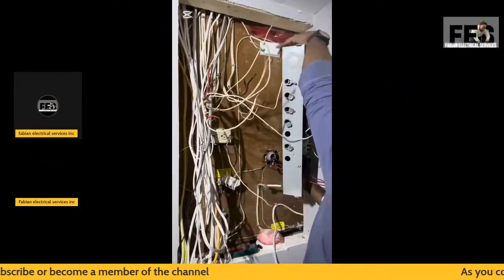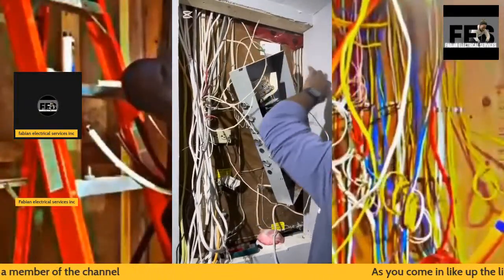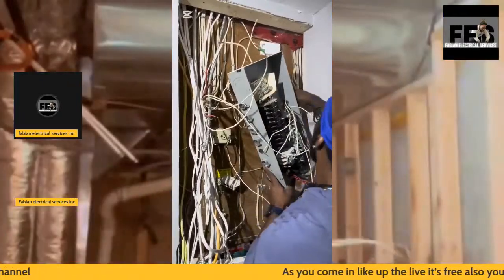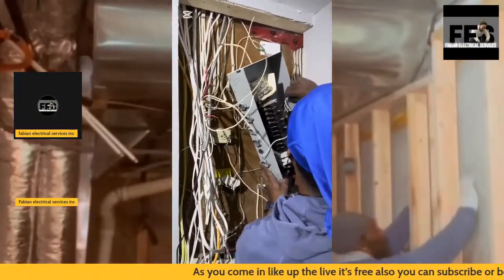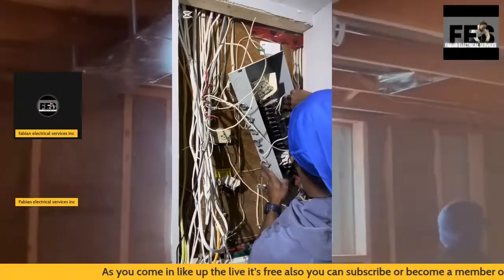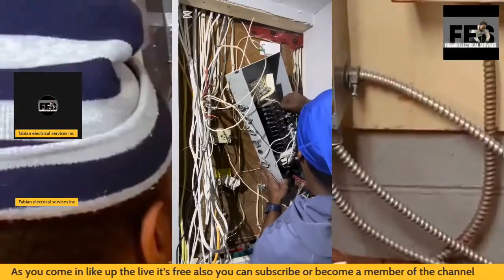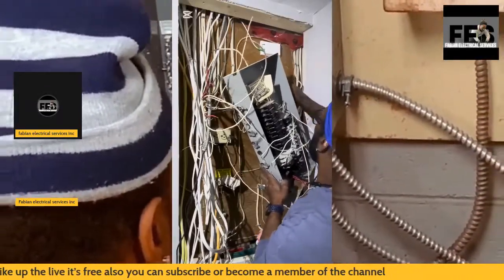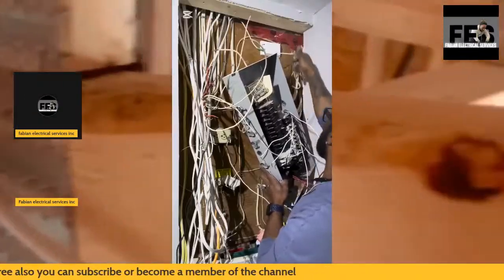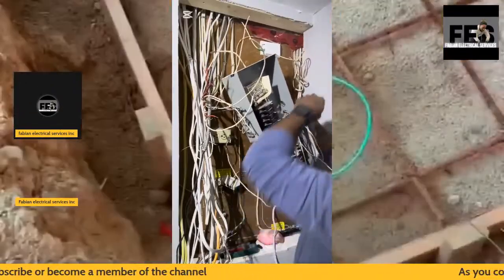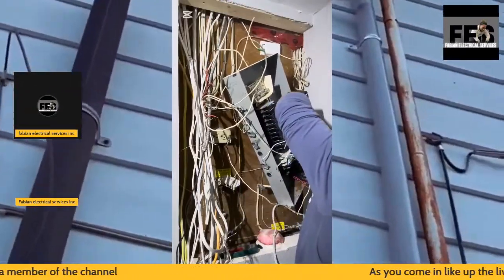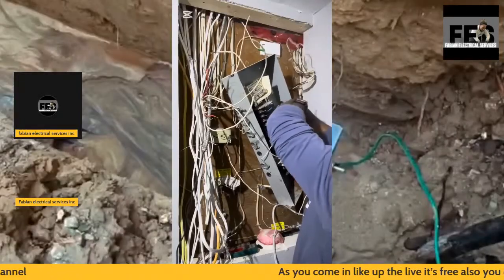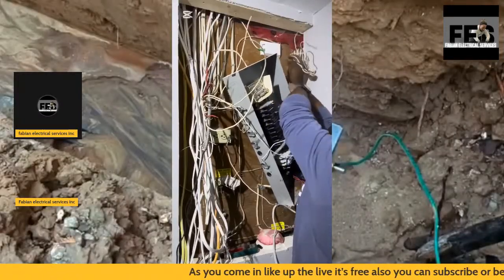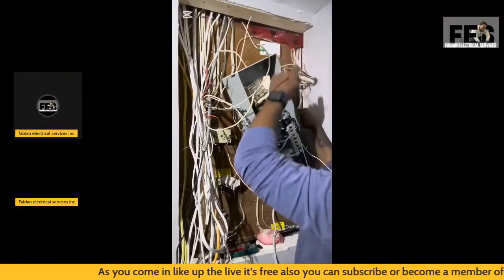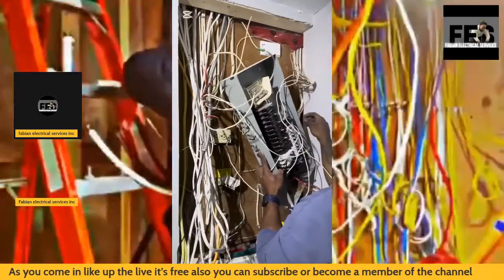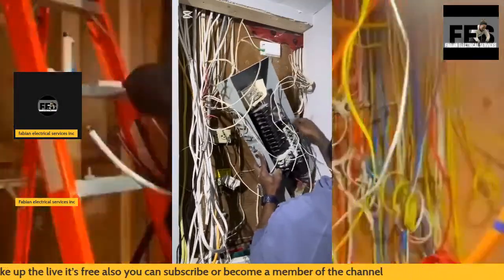Grounding and bonding. We spoke about that when we first started. Breaker sizing. Let's get into breaker sizing. You see this a lot in homes where some people will install, let's say, a 20 amp breaker, and they're going to try to install maybe a 30 amp wire on there.